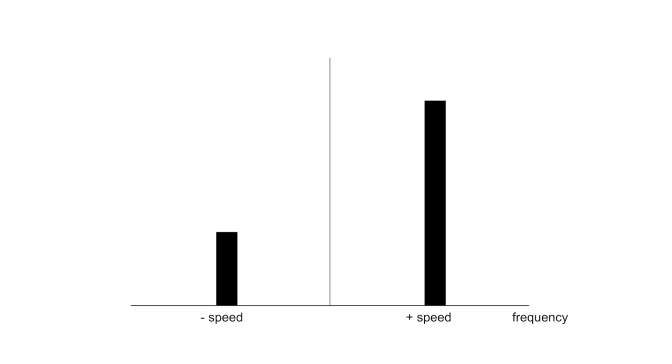Now please imagine the spectrum graph. It is a little special because it contains the positive frequencies and negative frequencies. The amplitude of motion in rotation direction we draw to positive part. The amplitude of opposite motion we draw to negative part. This spectrum is called full spectrum. Splitting of amplitudes to positive and negative frequencies contains next information for analysis.